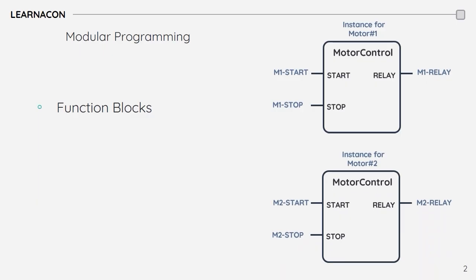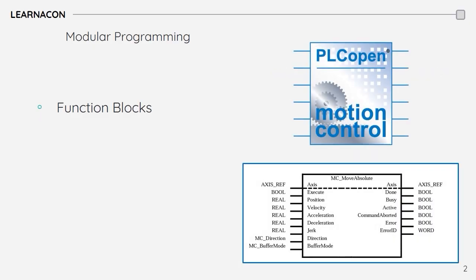For some advanced control concepts, like PID, you may find a library of function blocks in your PLC software tool. Most often, these blocks are protected against changes and are provided with an input-output description and an operation manual. For some other control topics, such as motion control, there are globally accepted standards developed by international entities like PLC Open. In this particular context, the method to enable, move, stop, and reset a position-controlled axis has been implemented in form of a function block library.